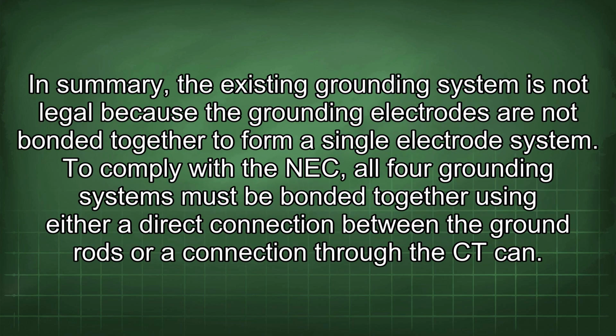In summary, the existing grounding system is not legal because the grounding electrodes are not bonded together to form a single electrode system. To comply with the NEC, all 4 grounding systems must be bonded together using either a direct connection between the ground rods or a connection through the CT can.